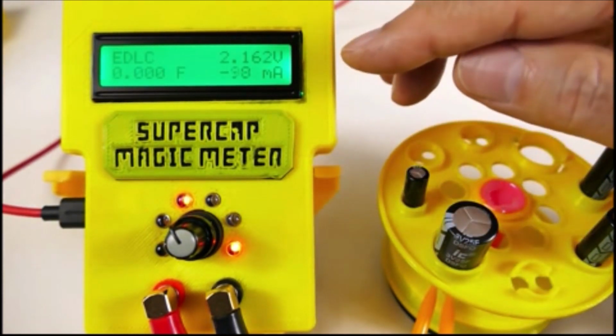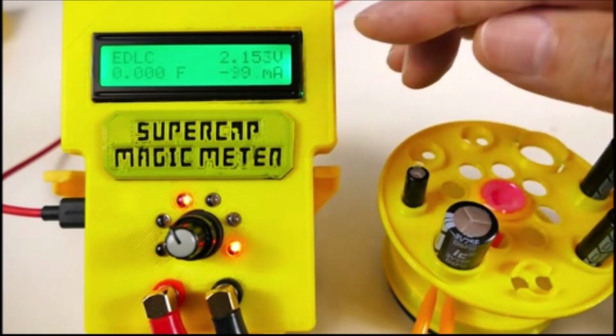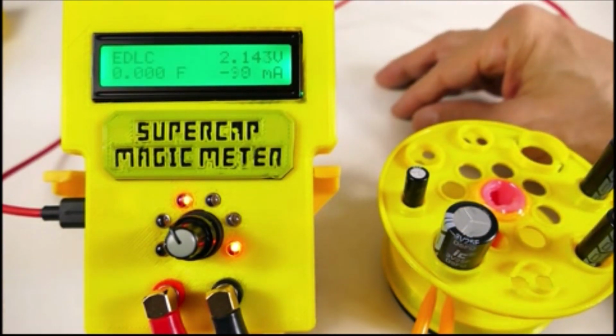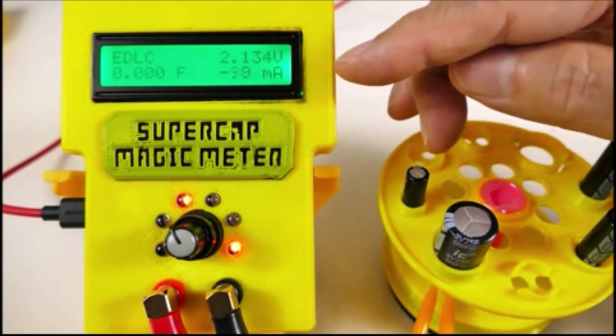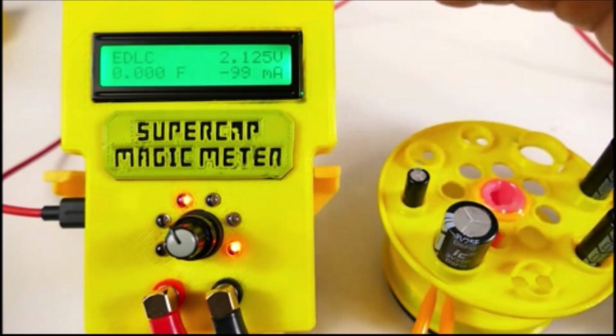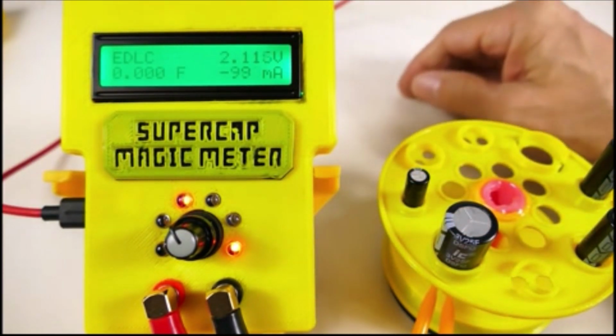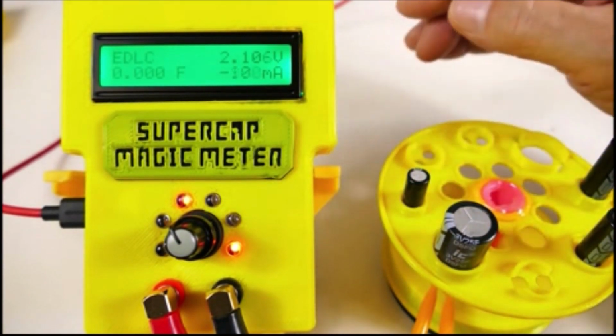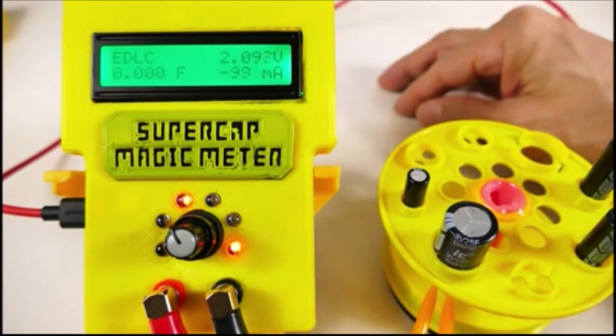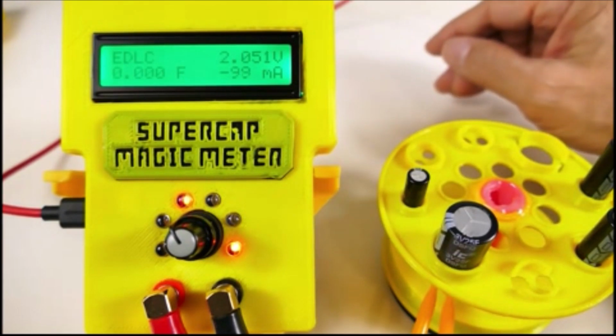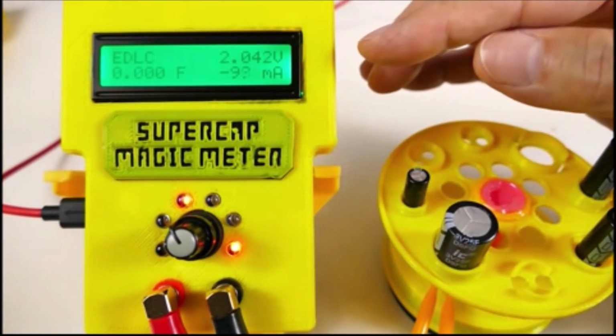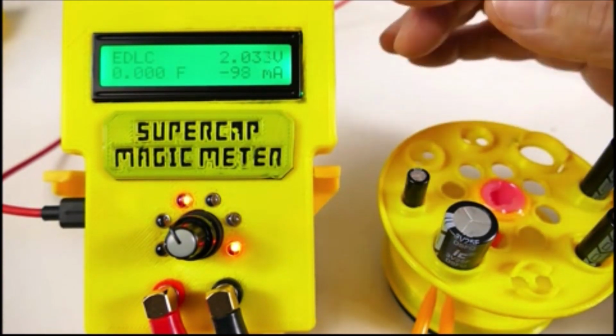The current is bobbling between 100 and 99 milliamps, but that's taken into account in the measurement, so it's measuring this all the time to make sure it's always got the right current. And it's 40 millivolts away from taking a reading.